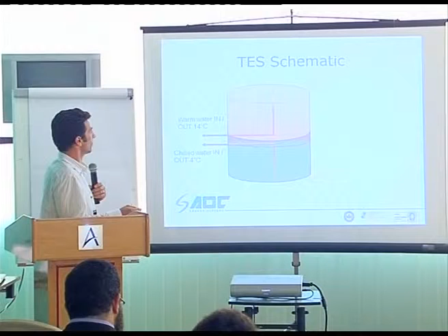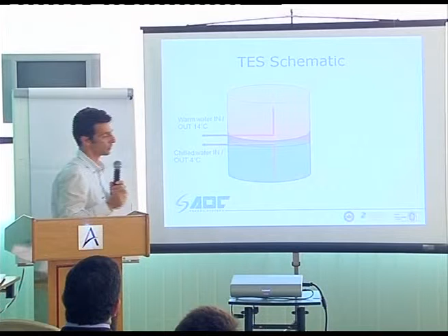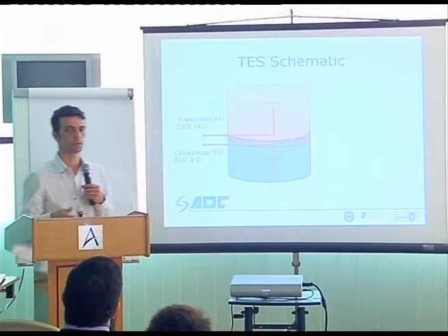You cannot control it, but you try to design your diffusers in order to produce this very shallow thermocline. One thing: the higher the tank, the more you can store on top of each other, and the less the percentage of thermocline that you will have, so the more efficient your tank is. But at the same time, the higher the tank, the more pressure you will have at this edge, and the thicker the shell plate will be for you. So come outside your mechanical or electrical engineering and think about structure and materials, and the thickness of this shell at the bottom of the tank, and that will cost you more money to build a higher tank than to build a short and wide tank. A short and wide tank means every 1 meter of thermocline is a lot more percentage of your volume and more inefficiency in your tank.